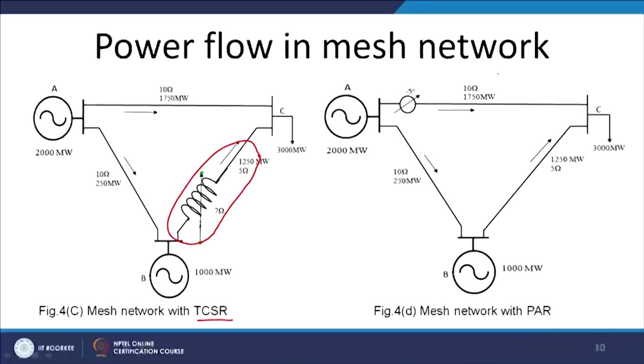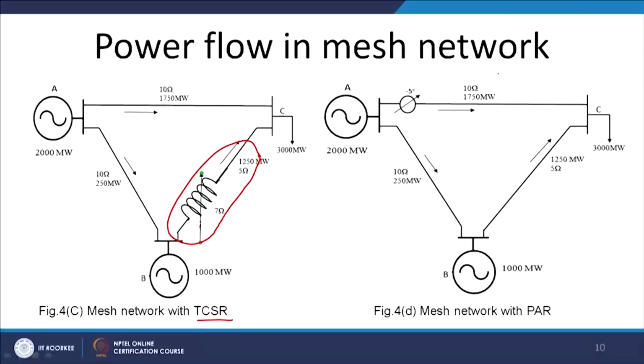Instead of injecting a series reactance, capacitor or inductor, we can insert a phase angle regulator which will increase the delta, the phase angle between point A and C, thus it can increase the power handling capability of the line. So these are the three solutions available, and depending on the thermal limit, the environmental condition, dielectric limit, current values, and all those considerations, a different solution will be chosen. So for the same point in a different ambient we may choose different solutions. Different kinds of FACTS devices will provide a unique solution for a particular case.